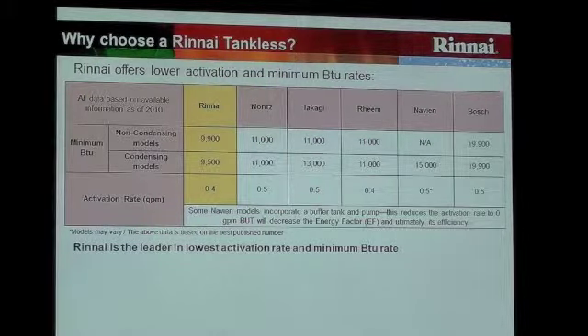So we're only burning 9,900 BTUs. Whereas if he turns that tap a little further on, he might be activating the high fire, and it may flow up to maybe 15,000 or 22,000 BTUs. So that flow rate is important. The lower the better. So we've gone through a lot of effort in this home, for instance, to reduce the amount of hot water we're using. We've got 10 different things we're doing to reduce hot water. So this feature, what you're talking about here, is enabling us to go with a lower flow. Yes, absolutely.